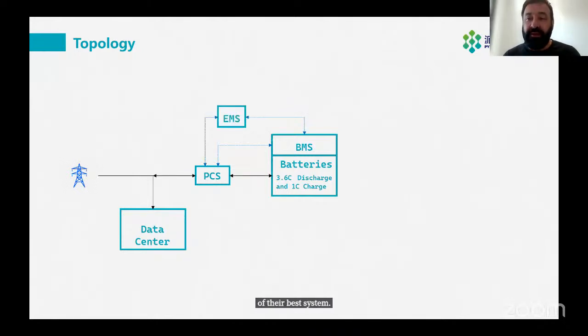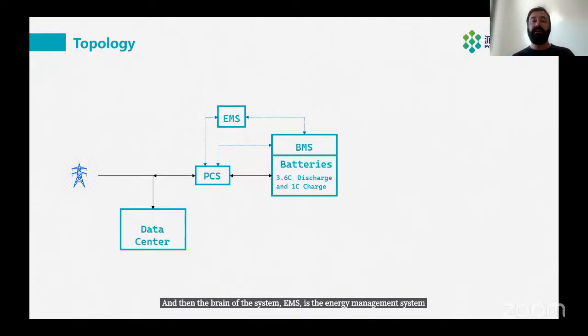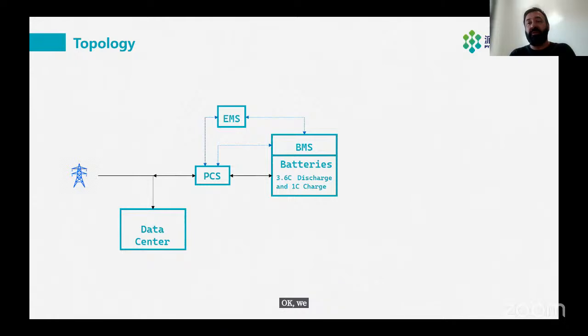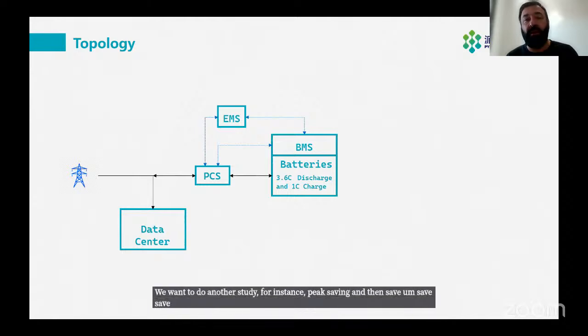Then the brain of the system is the EMS, the energy management system, that manages the whole structure—the battery, how it's charged, when it's charged, and any additional supply from diesel generator or PV side. This system can be set to manage all this energy, taking into account if you need to do a backup, or another strategy like peak saving, reducing OPEX thanks to the reduction of consumption from the grid.